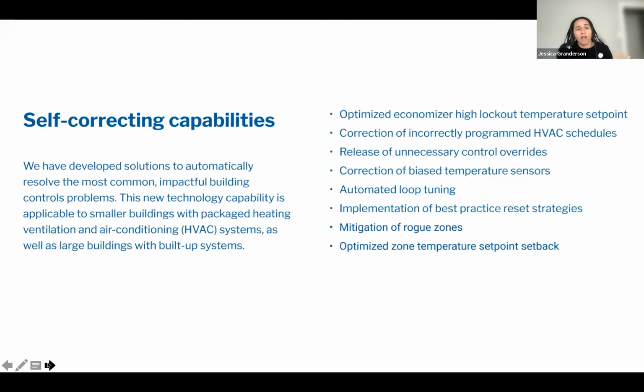We've focused in this work on the most common and the most impactful controls problems that we see time and time again in our facilities. And we can apply this to smaller buildings with packaged HVAC systems, as well as the larger buildings with the built-up systems, so long as they are running the FDD software in the first place. When I say we can correct problems, I'm showing in the bulleted list on the right what we're actually talking about. Economizer lockout temperatures, incorrect schedules, releasing manual overrides that are no longer needed, correcting biased sensors.